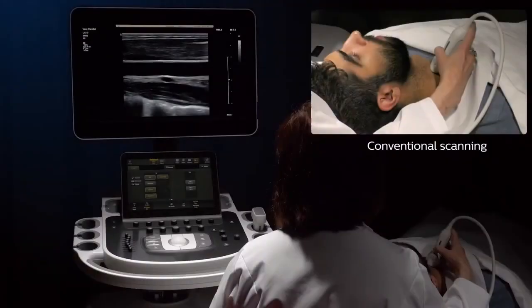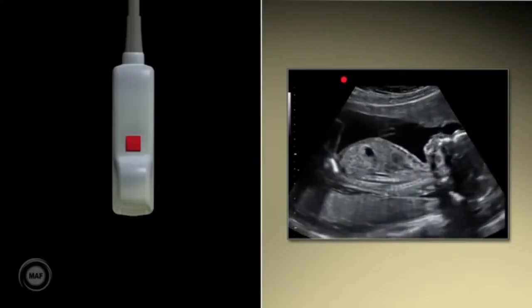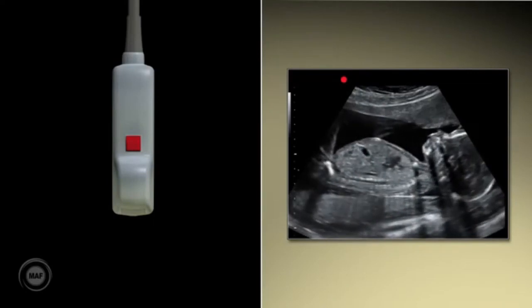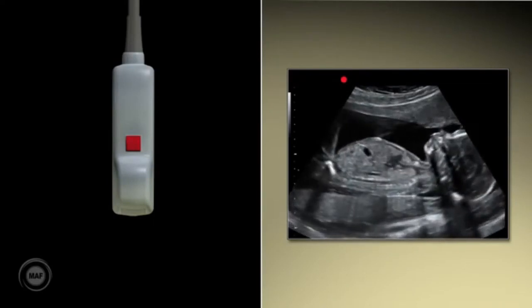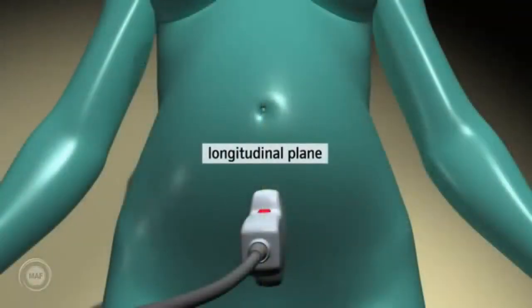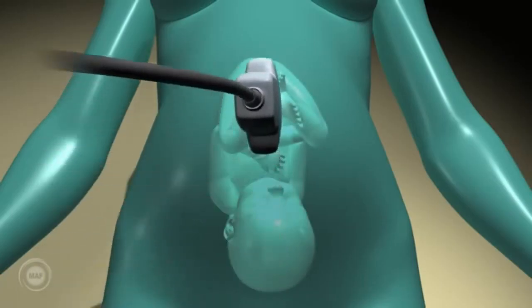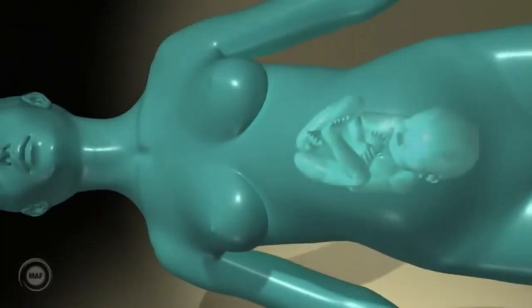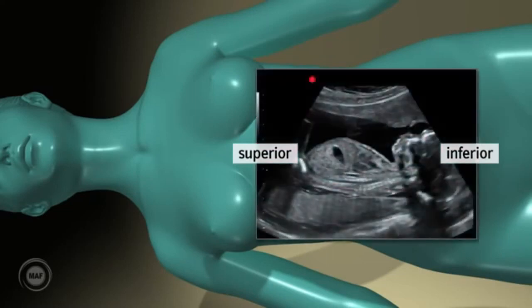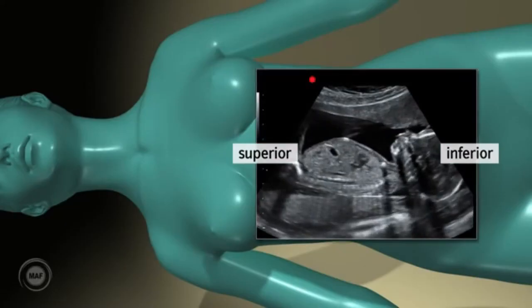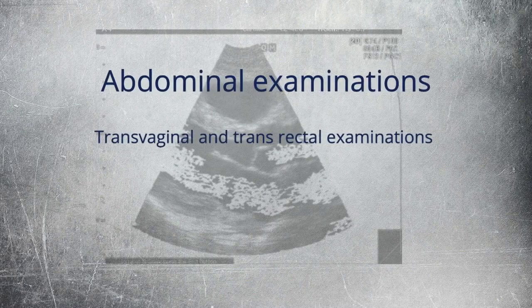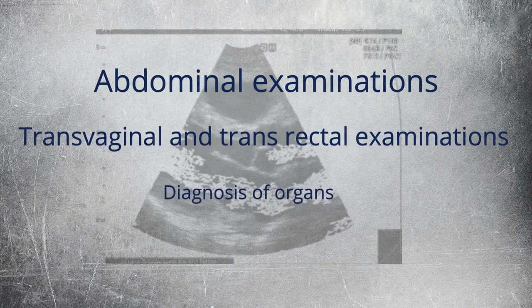Second type of probes are convex probes. The convex ultrasound transducer type is also called the curved transducer because the piezoelectric crystal arrangement is curvilinear. Moreover, the beam shape is convex, and the transducer is good for in-depth examinations, even though the image resolution decreases when the depth increases. The footprint, frequency, and applications also depend on whether the product is for 2D or 3D imaging. The convex transducer for 2D imaging has a wide footprint and its central frequency is 2.5 megahertz to 7.5 megahertz. You can use it for abdominal examinations, transvaginal and transrectal examinations, and diagnosis of organs.